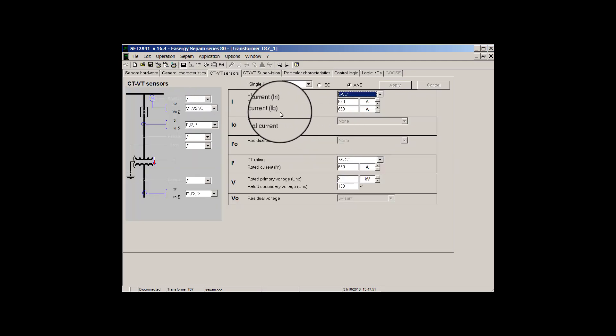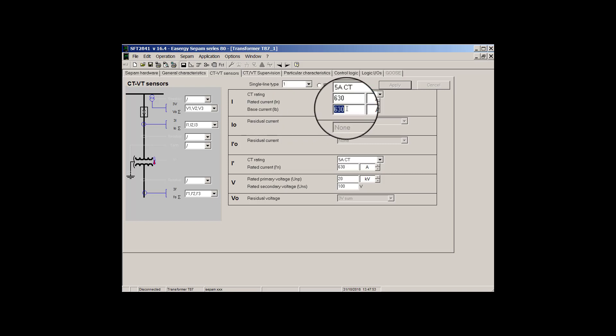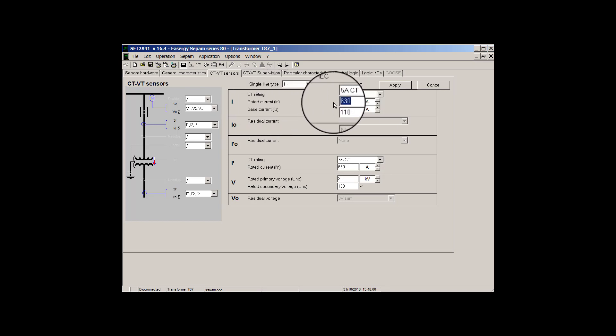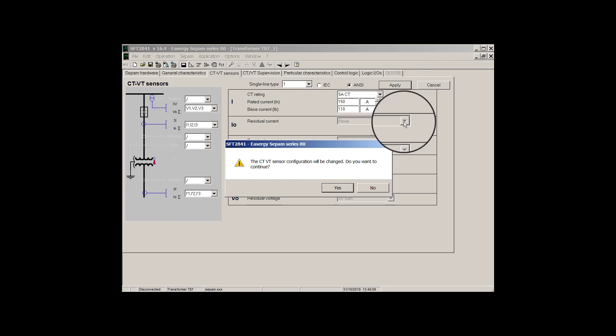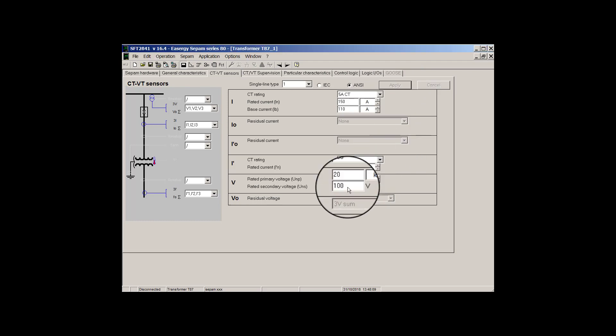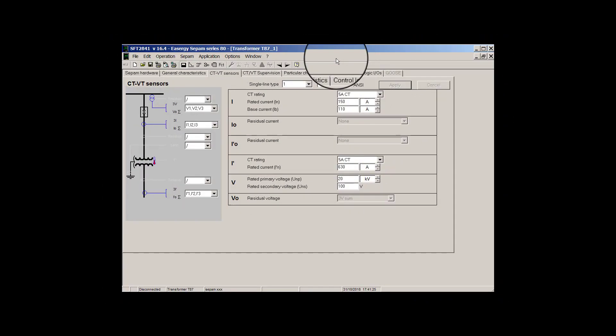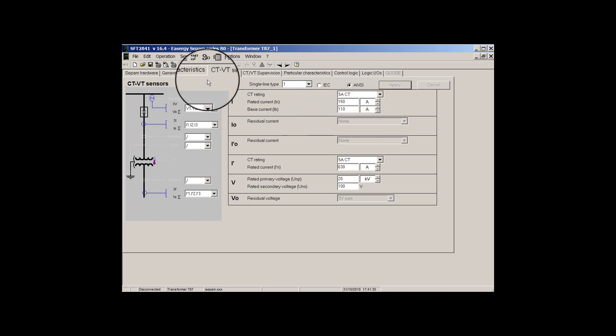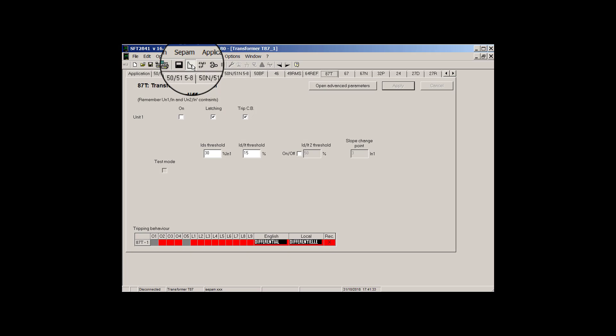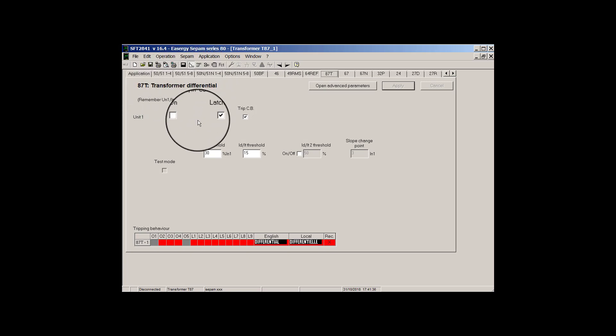So here in CT/VT sensor part we set 110 amp as base current of transformer. And for sizing a correct CT we should size a CT around 110 amp, but in range of 11 to 275 amp. So I will choose 150 and I will set it. So we sized in range 11 to 275 correctly.